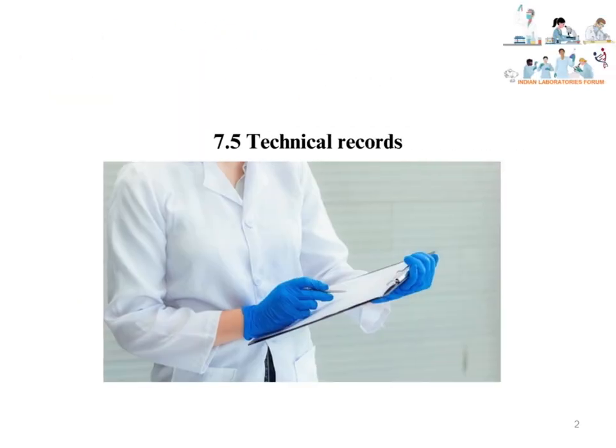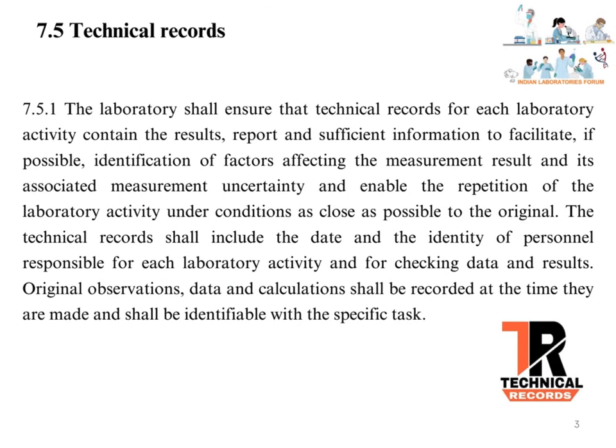Clause 7.5 – Technical Records. The laboratory shall ensure that technical records for each laboratory activity contain the results, report, and sufficient information to facilitate, if possible, identification of factors affecting the measurement result and its associated measurement uncertainty.